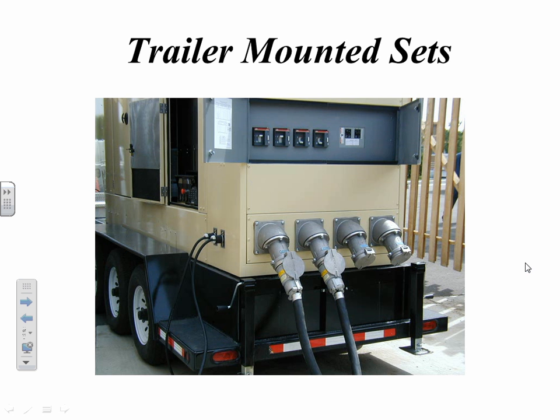Okay? So we'll call this leg 1, leg 2, and this is leg 3. In this configuration, there's a nasty thing that happens. So this is actually neutral down here. So in a 120, 240, 3-phase system, in this configuration, let's say the coils had 120 volts. Okay? So between leg 1 and neutral, these two, we got 120 volts. Same on this side, so that's 120 volts. That means we have between leg 2 and leg 1, we've got our 240. This up here, because we can't get to neutral real easy, this is what they call a wild leg. So in most operations, most cities that use this, it's not real effective anymore. So 120, 240, 3-phase is kind of going away, and they're using 120, 208 in its place. So this is the only one that has a wild leg.